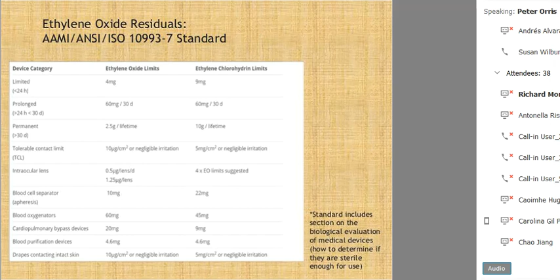The processes for sterilization have 3 levels to them. One is a preconditioning, which will take several hours. The second is the sterilization phase itself, in which in the sterilizing chamber, the ethylene oxide is administered. And finally, there is an aeration stage in which the aeration chamber, a separate chamber, is heated and the ethylene oxide off gases for several hours after this point. There are standards both internationally and for us in the United States, and consensus standards within the industry about the use of ethylene oxide. None of these standards, nor the estimate of the residuals, have taken into account potential community exposures related to the carcinogenic effect.